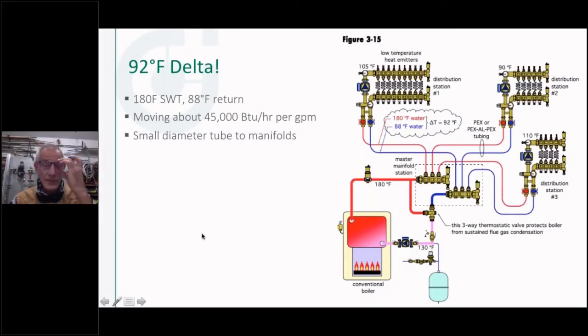So what about a system where I could run a 92 degree delta T? Look at this system here. I'm using a conventional cast iron boiler in this case. I'm going to run that at 180 degrees. And now out here on my radiant, I only need about 105 degree supply temperature. So all I need to do is take some small diameter PEX tubing, because I'm going to run this huge delta T here. I could probably feed that manifold, maybe there's 10 loops on that, with half-inch PEX, because I'm leveraging this delta T.